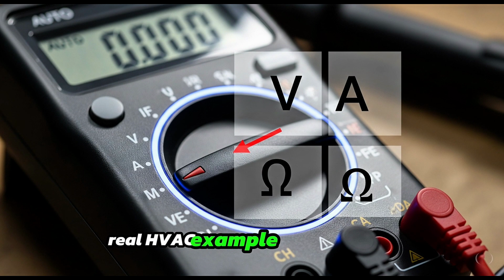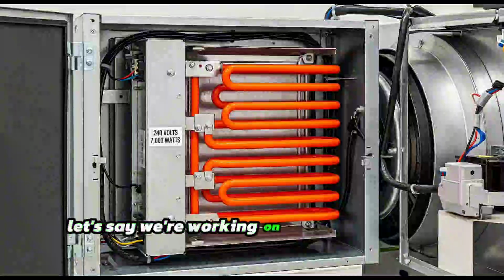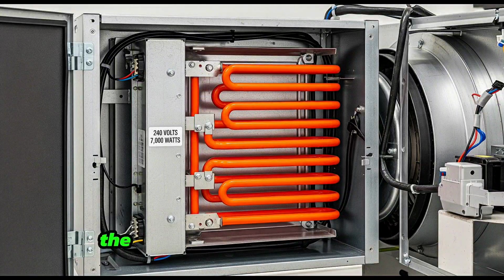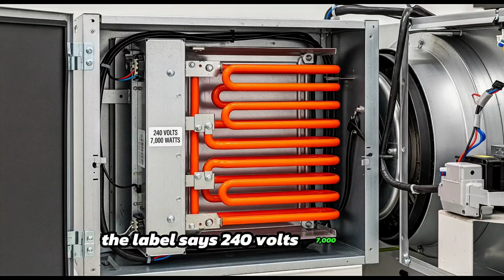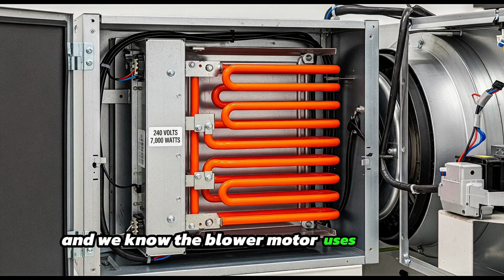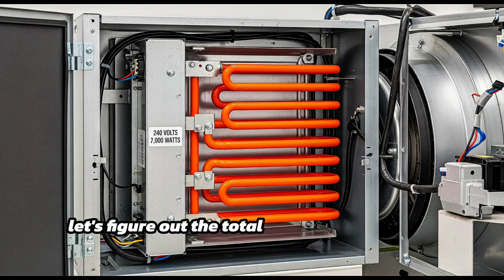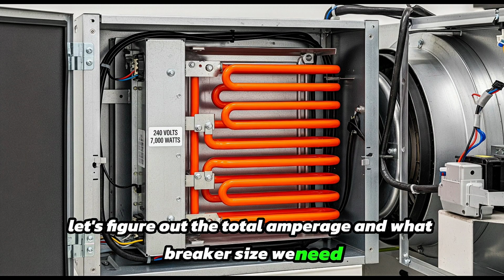Real HVAC example: an electric heater. Let's say we're working on an electric heater inside an air handler. The label says 240 volts, 7,000 watts, and we know the blower motor uses 2 amps. Let's figure out the total amperage and what breaker size we need.